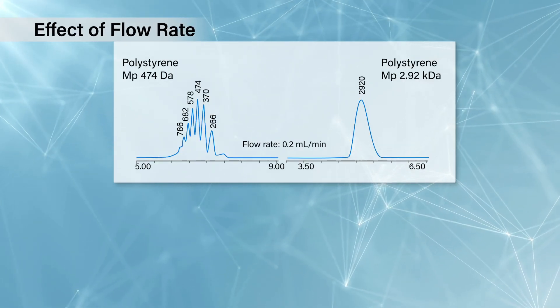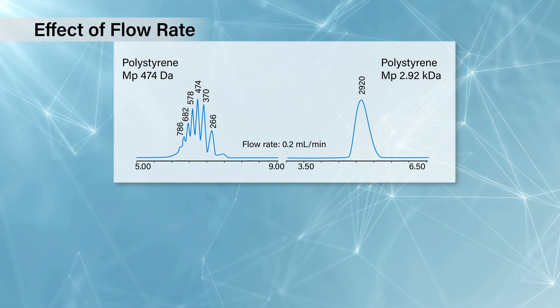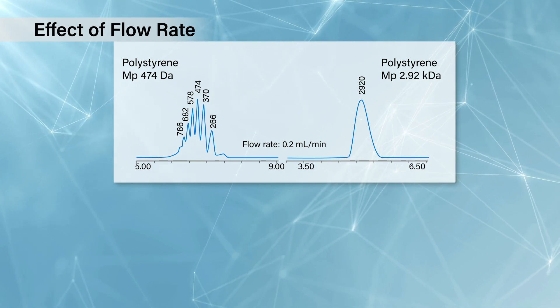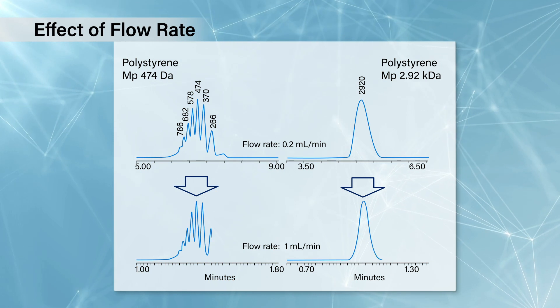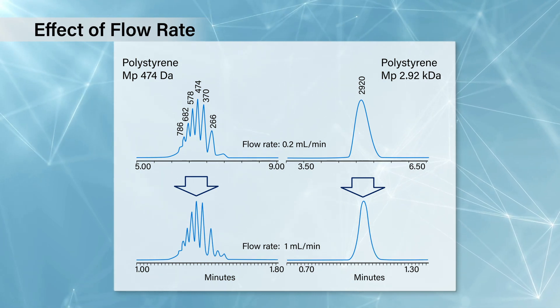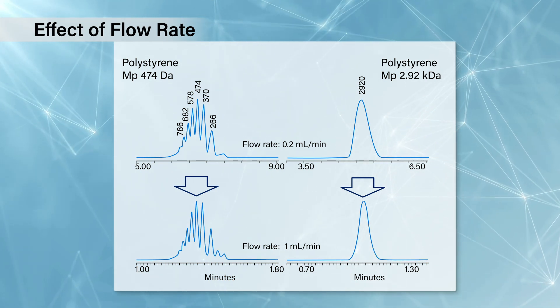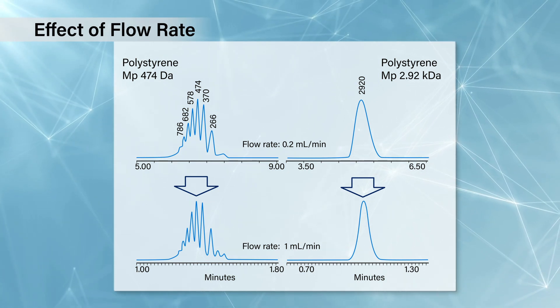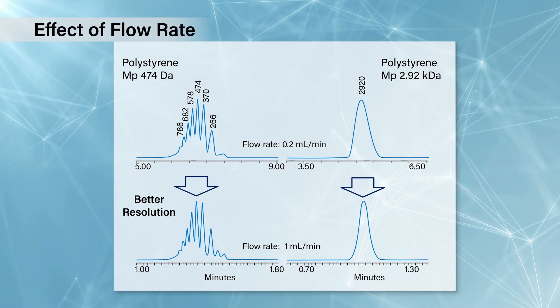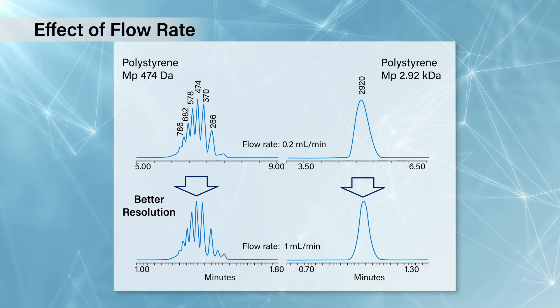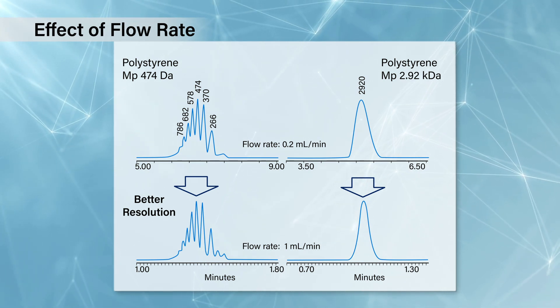Here we have an example of a low molecular weight polystyrene — a very low oligomeric sample around 400 Daltons and one up at 2.9 kilodaltons — and you see the effect of changing the flow rate. The top traces are at 0.2 ml per minute and the bottom ones are at 1 ml per minute. For those low molecular weight oligomers, you can see that by increasing the speed, you're actually increasing the resolution of your experiment, which is perhaps counterintuitive to those working with traditional GPC.